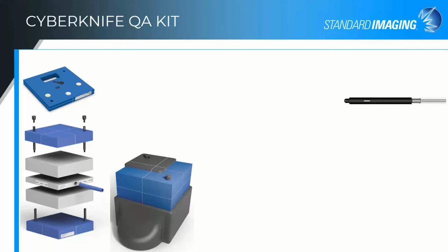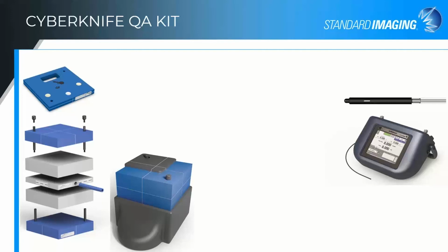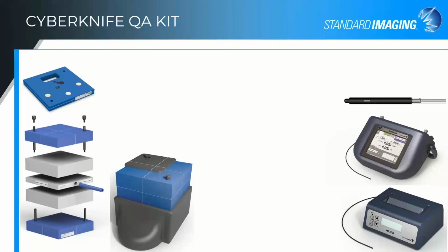Detectors commonly used with the SDVP include our Exradin A26 micropoint chamber, the ideal reference class micropoint chamber with a spherical spot size of 4.3 millimeters, and our scintillators. The W1 scintillator is a dual-channel detector used in combination with our best-in-class SuperMAX electrometer. The W2 has a 1x1 millimeter fiber and is used in combination with the MAX-SD for water scanning purposes. Both have a KQ of 1, making them ideal for stereotactic QA. My colleague Shannon did a fantastic presentation on small fields last week that you may want to view by accessing it on our website.